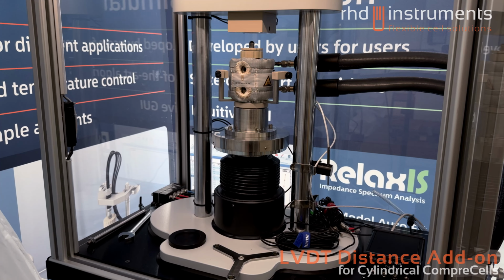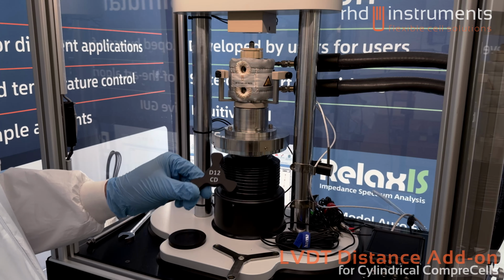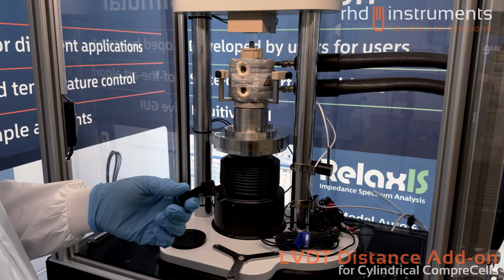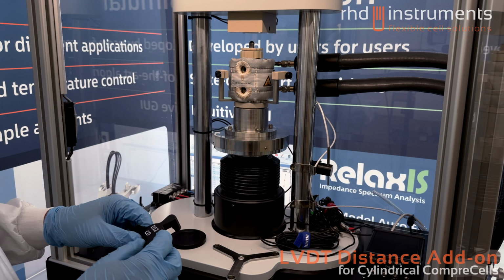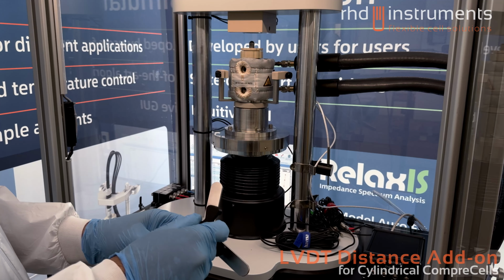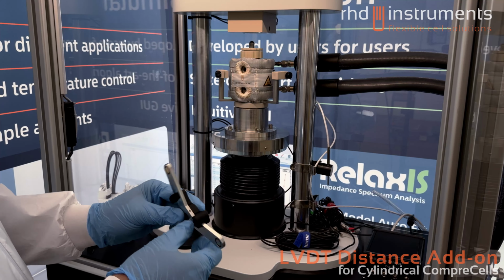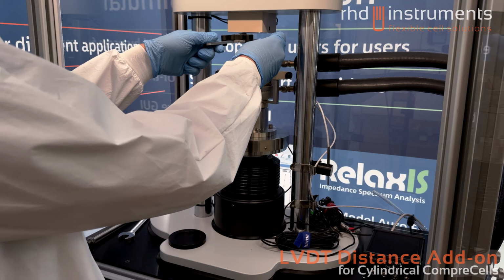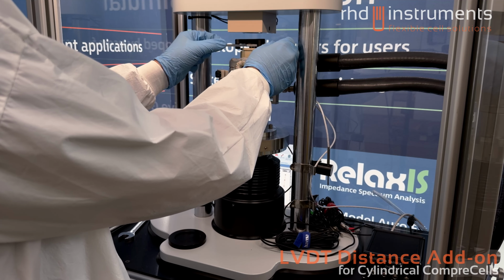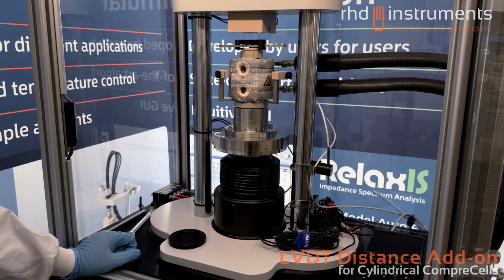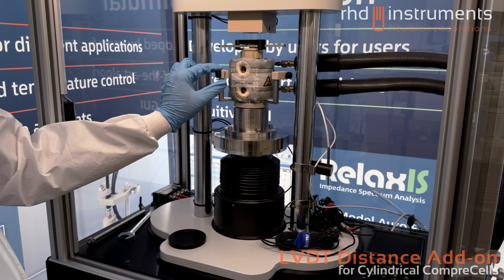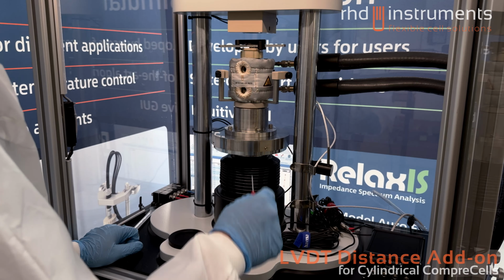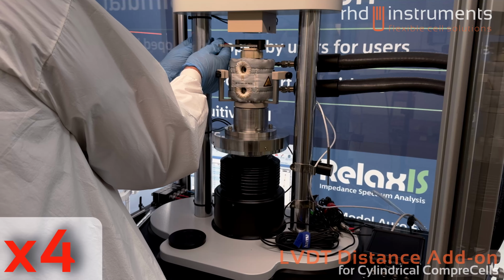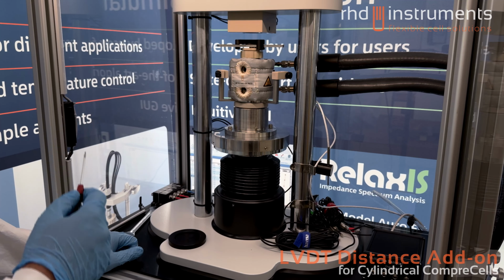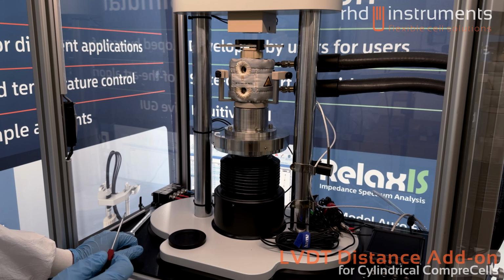Next, we want to mount the cantilever on the cell. We will use the cantilever placement aid that is available in different versions, for example for 12mm, 10mm CompreCells and for CompreDrive and CompreFrame. I will attach the placement aid on the cantilever and place the assembly on the upper piston. And then I rotate the cantilever in a way that the sensor holders are aligned with the cantilever. After that I can tighten the grub screws. Please make sure that you do not rotate the cantilever after tightening the grub screws, because this might damage your sample.